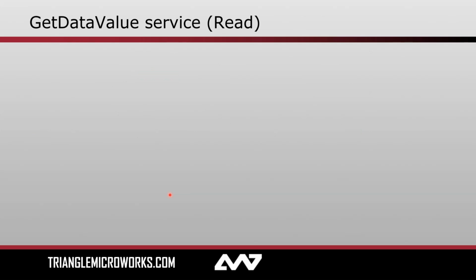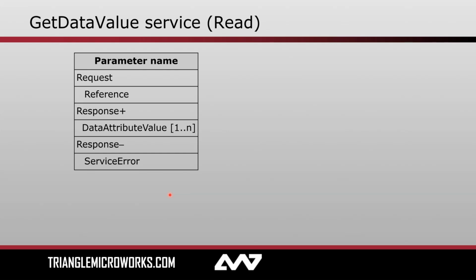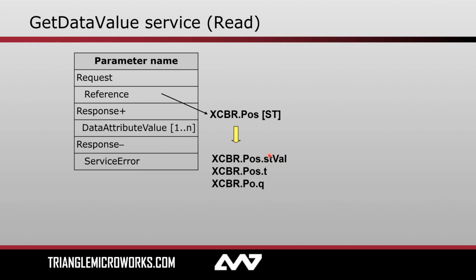Well, the most basic way to do it is to issue a read. When we do this, the client can go out and issue a request, and it passes a reference to the particular piece of data that it wants to request. So in this first example, notice that we've requested the entire Pos, or position, data object, noting that this will have several children below it. Now, when we issue this read request, we actually do provide a functional constraint, or FC. In this case, our functional constraint is ST, or status value. So we're basically asking, hey, server, I want this particular circuit breaker, this data object under it, and give me all the data below it in the tree that has the functional constraint ST, or the status values.